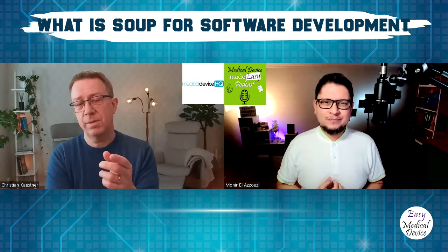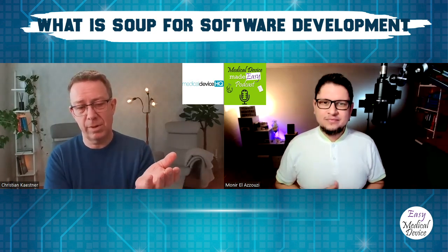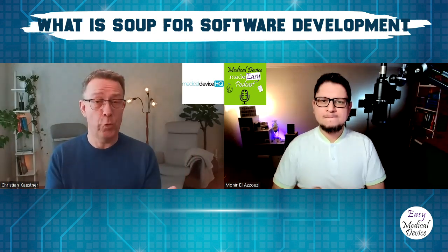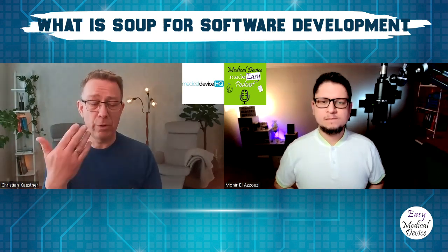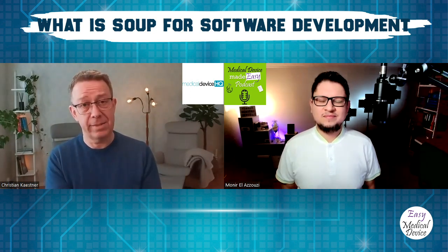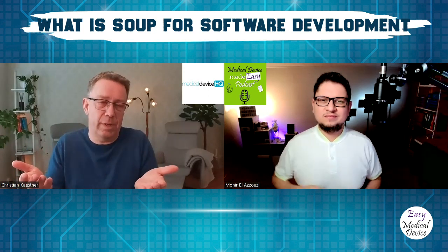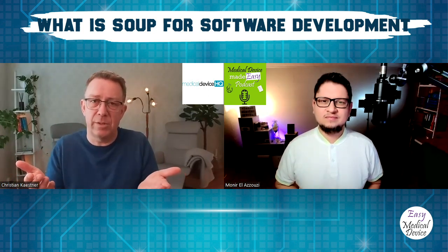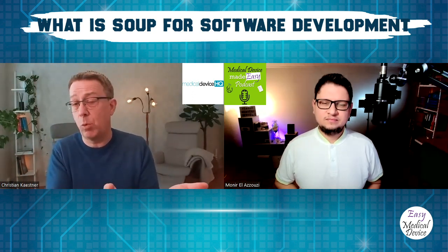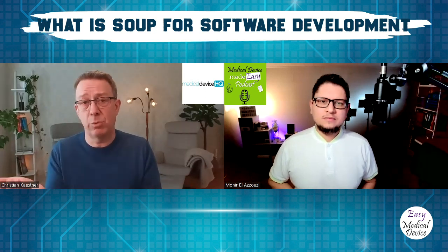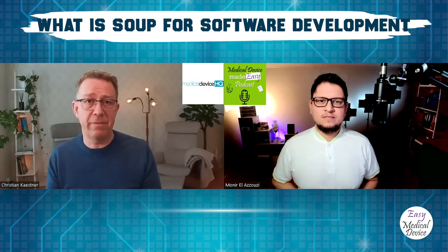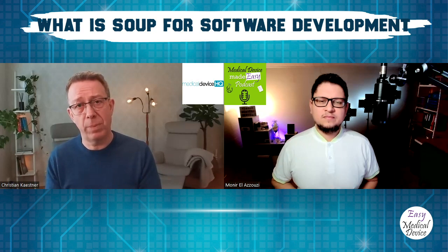Yeah. But just a comment on a software supplier claiming compliance with 62304. Hopefully they know and understand the language. So you could approach them and say, could you please share your risk management file? And if they can, then you can hook into that. It will of course make your start working with that piece of software easier, because you can see and verify what they've already done. And perhaps you can even leverage it if they provide this documentation. But if they don't provide any documentation, I don't see any benefit of them claiming that they are 62304 compliant.